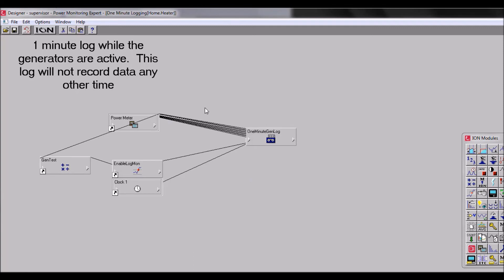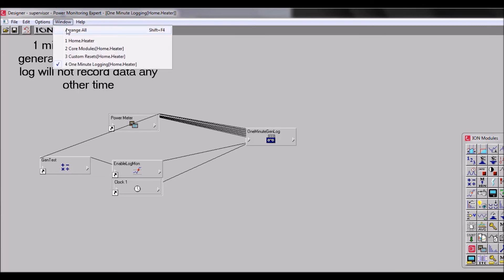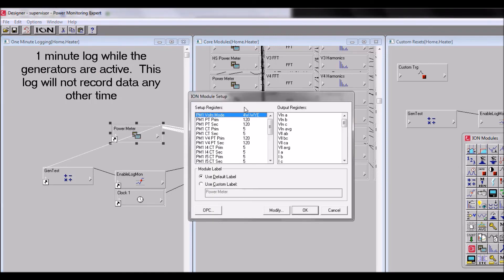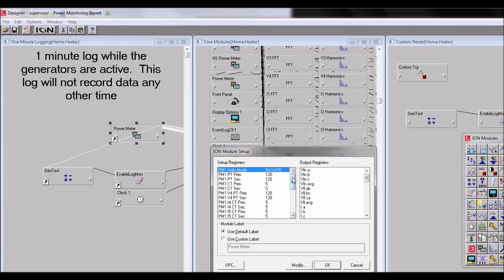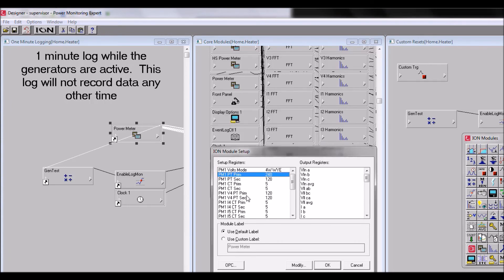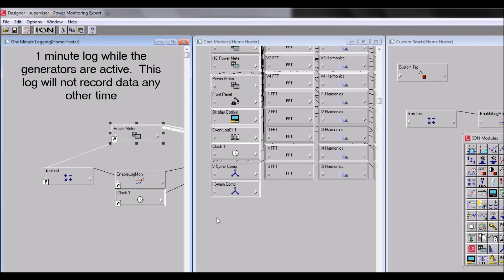Some quick notes on a shortcut module. First, any change made in a shortcut module will be reflected in the original. So if we go to our power meter module and change the PT primary to 240, click OK, then click OK, then click OK again, we'll notice that the original power meter module now has a dotted line meaning that is an unsaved state.